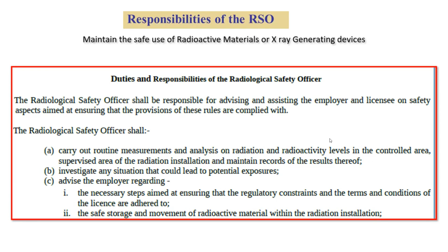So they have to follow the room size and the shielding material, the position of the machine where it is going to be, which floor it has to be on, what departments should be surrounding it, how the corridor should be, and that there should not be a waiting area for pregnant patients. So everything comes in the project planning. It is the responsibility of the RSO. For all installations, it is applicable.